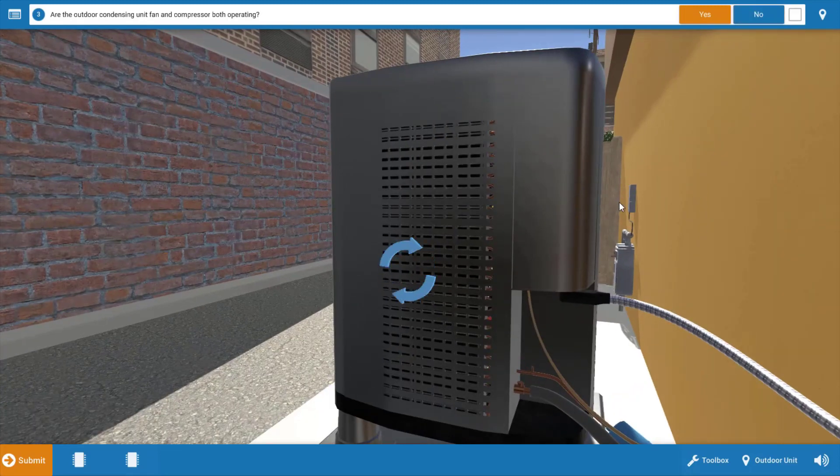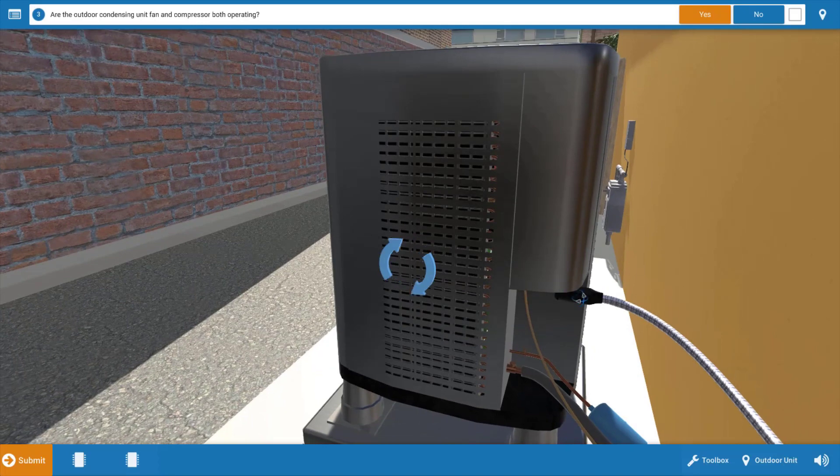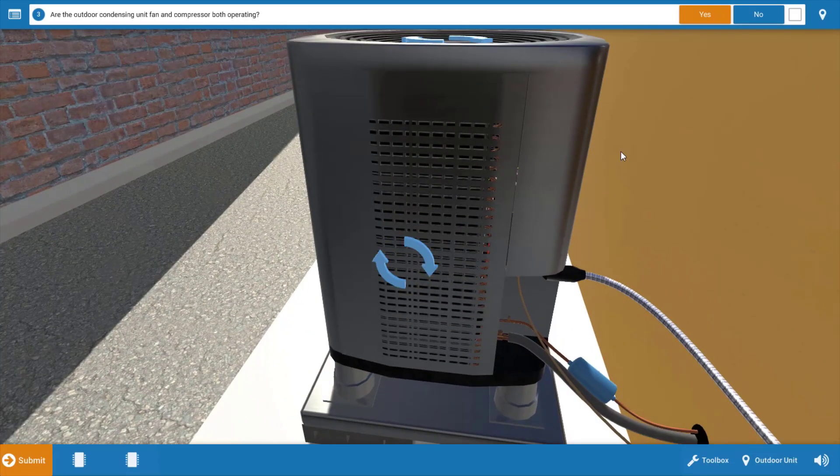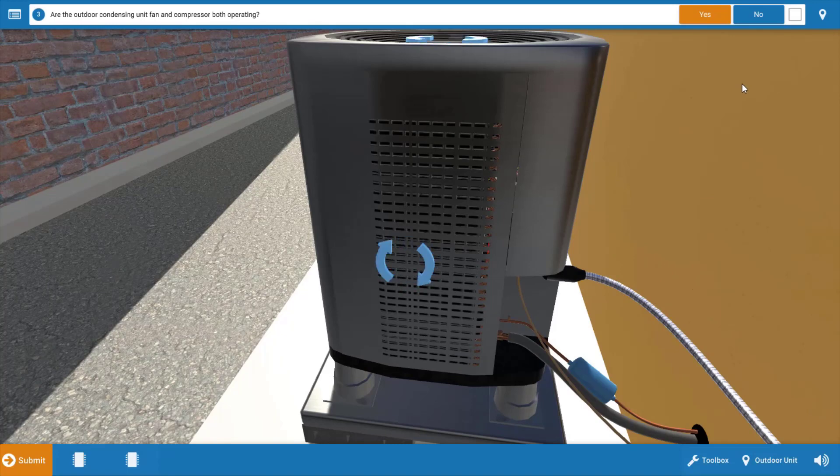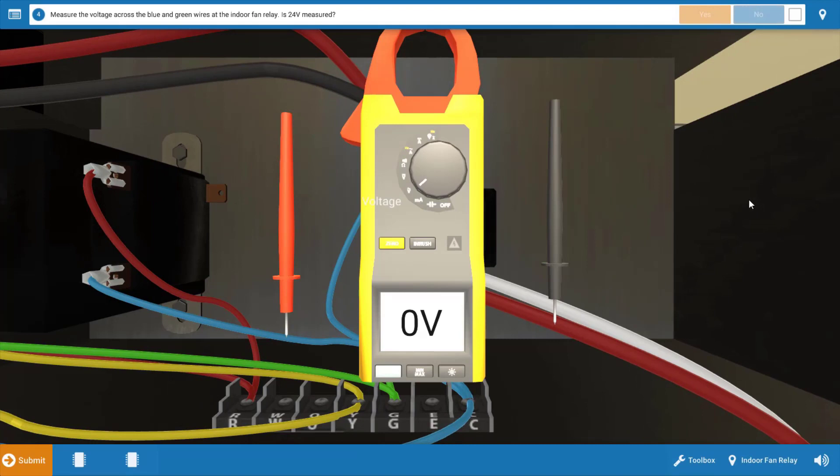We're going to proceed to the outdoor unit. Once there, we can see that the compressor, as well as the condenser fan motor, are both operational. So the outdoor unit's working just fine. We have no operation of the indoor fan motor. So we're going to click yes on the procedure guide that we verified those two motors are on.